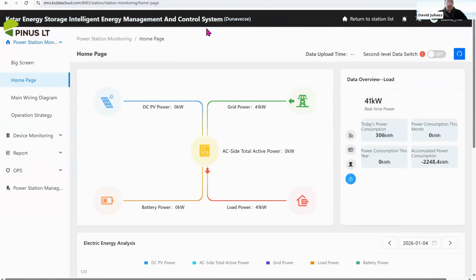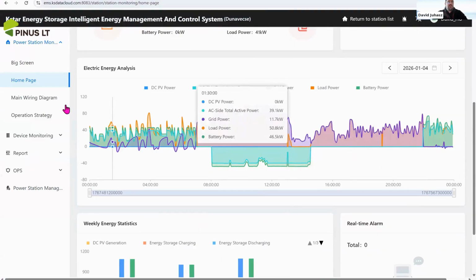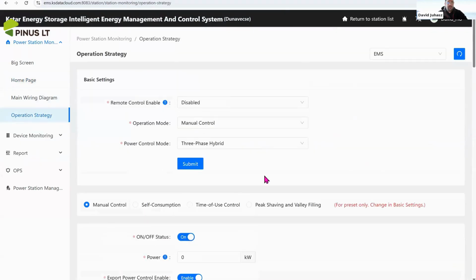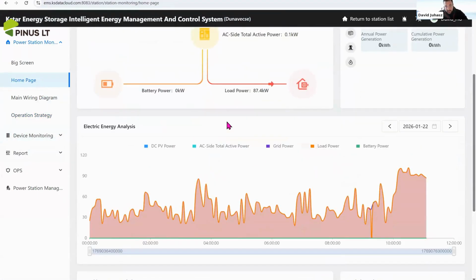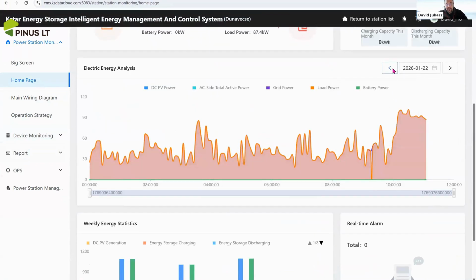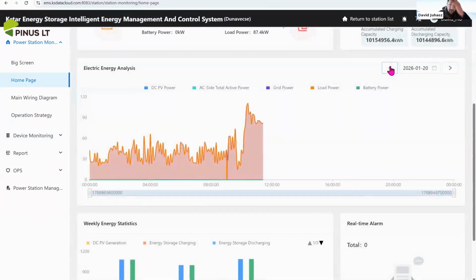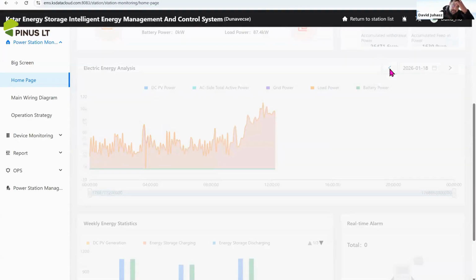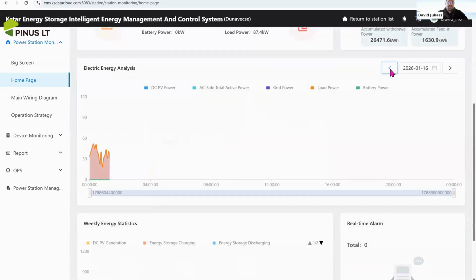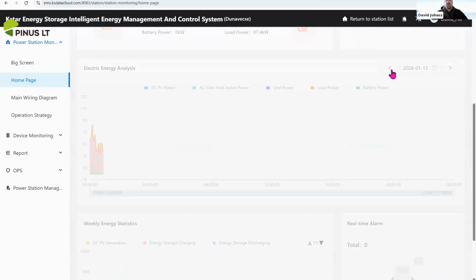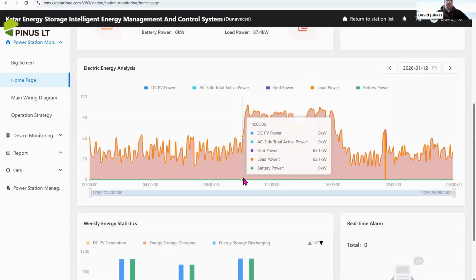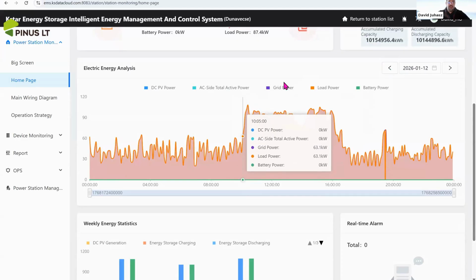Okay, and here is another site which is controlled by a third-party device. If we go to operation strategy, we see it's in manual mode. That means that the third-party device is reading and writing registers of the system. And if we go back for a better day, we can see that because in that site there are third-party PVs on the site, therefore we do not see the PV power because it's only coupled on the AC side.